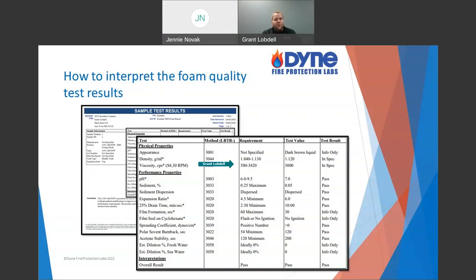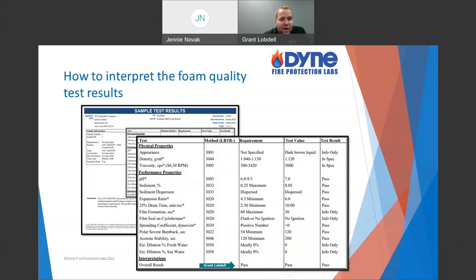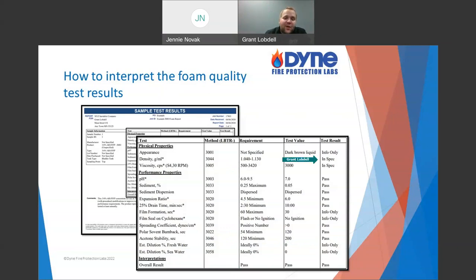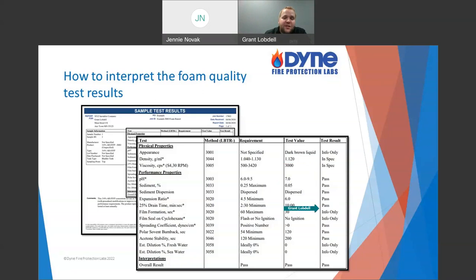That's the general overview. There's other info we can provide — including how diluted the foam is. Your overall result is always presented at the bottom of the report at Dyne. If there are any fails, we would recommend replacement or investigation depending on the situation. You'll see in-spec/out-of-spec on physical properties. If something is out-of-spec on a physical property, that doesn't mean it fails — we look at performance properties to determine pass or fail. Physical property readings are just clues; performance properties are the actual determination.